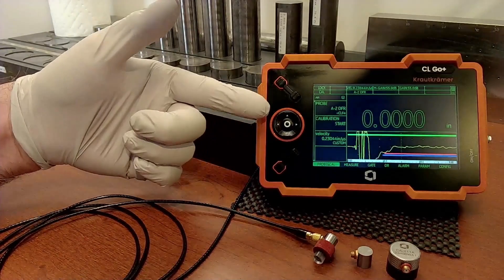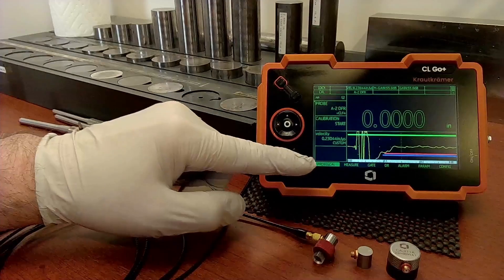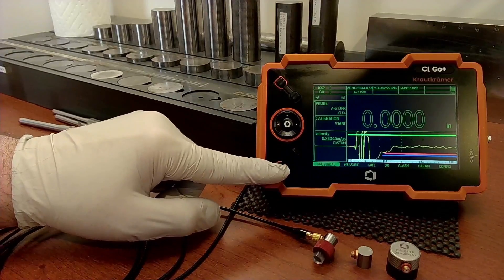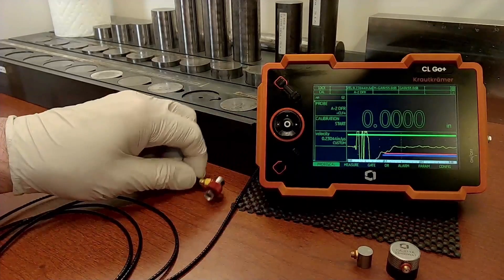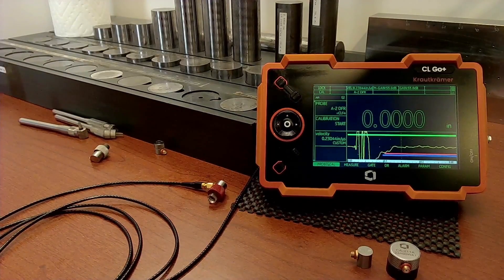We have booted into the precision thickness mode. I have a simplified set of the menus available. I have taken the opportunity to assign one of my function keys to calibrate. So normal thickness gauge, we power up, we calibrate, and we go measure things.